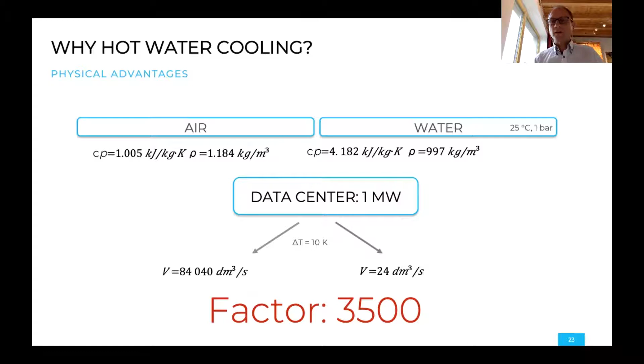So just a comparison, if you have a data center of 1 megawatt and you cool that with air, and here are some numbers, but it means you need 84,000 liters per second of air to cool that 1 megawatt data center. If you use water, you only need 24 liters per second. So that's a massive factor of 3,500 between air and water. So it totally makes sense to have a closer look at water, despite that people fear water and electricity is a dangerous thing. So that's something you have, or we have addressed.